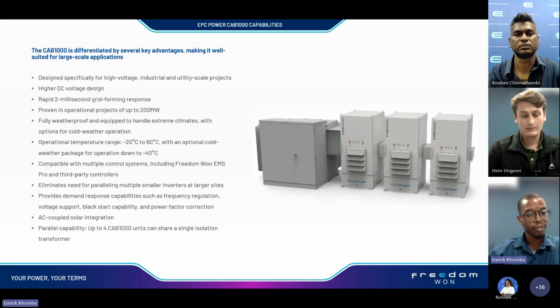As mentioned previously, there are demand response features such as frequency regulation and voltage regulation. There's also a black start capability provided, which requires installing auxiliary power for the control and cooling system for the inverter, and that is backed up through a UPS. And also, as mentioned previously, when on grid, you can generate excessive reactive power to correct the power factor of the load, because the inverter can operate in all 4 quadrants of the power circle.